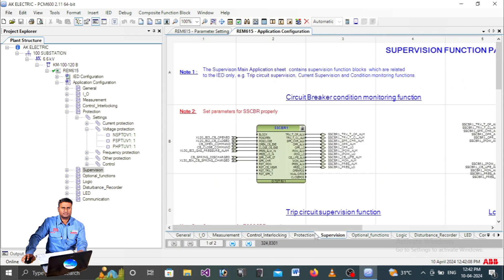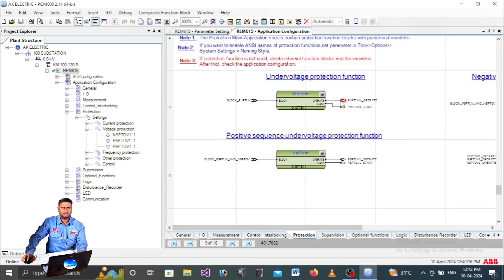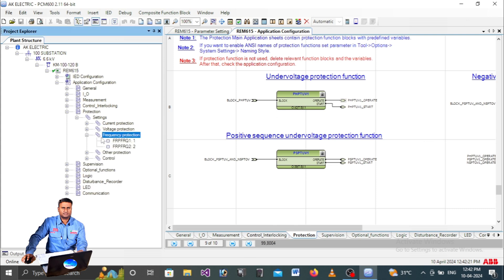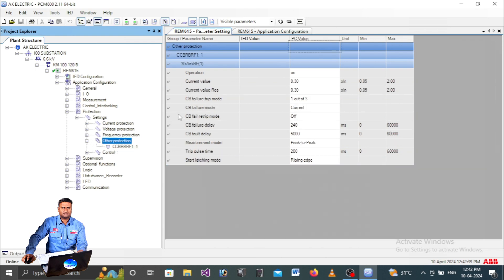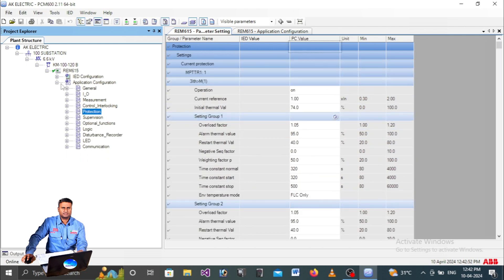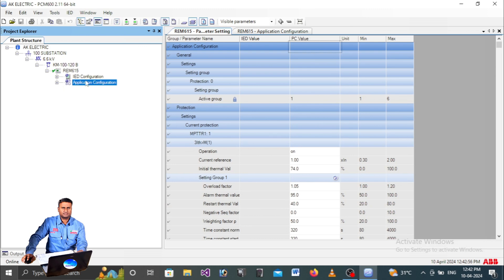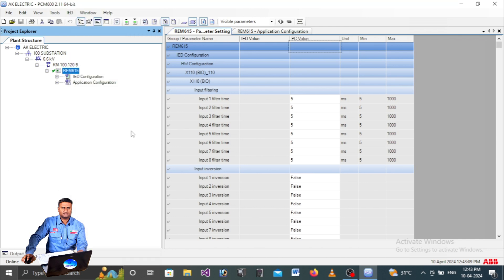You can see all settings here - current-related settings, voltage-related settings. You can also go to Application Configuration to see how the blocks are designed and connected. There are also breaker failure settings and motor standstill settings under Control. Remember, all these are default settings, not the current relay settings. To see actual settings, right-click the relay and select Read - only then will you get the actual settings. We will cover the Read option in another video.